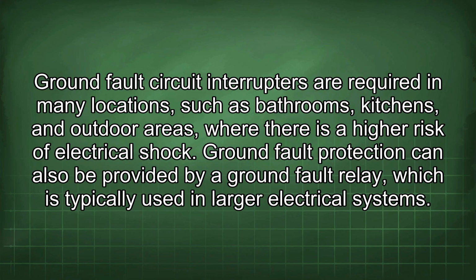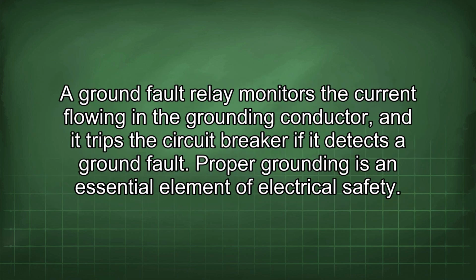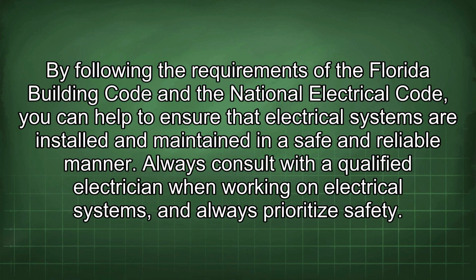Ground fault protection can also be provided by a ground fault relay, which is typically used in larger electrical systems. A ground fault relay monitors the current flowing in the grounding conductor, and it trips the circuit breaker if it detects a ground fault. Proper grounding is an essential element of electrical safety. By following the requirements of the Florida Building Code and the National Electrical Code, you can help to ensure that electrical systems are installed and maintained in a safe and reliable manner. Always consult with a qualified electrician when working on electrical systems, and always prioritize safety.